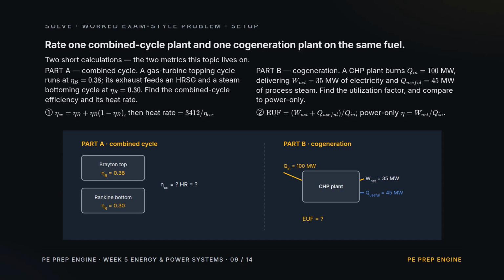Part B, cogeneration. A plant burns fuel at 100 megawatts and delivers 35 megawatts of electricity plus 45 megawatts of process steam. Find the utilization factor and compare it to the power-only efficiency. The plan, for Part A, combine the two efficiencies with the leftover factor, then invert for heat rate. For Part B, add power and useful heat over fuel in, and separately divide power alone by fuel in.